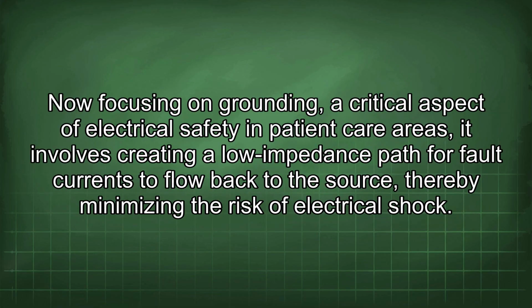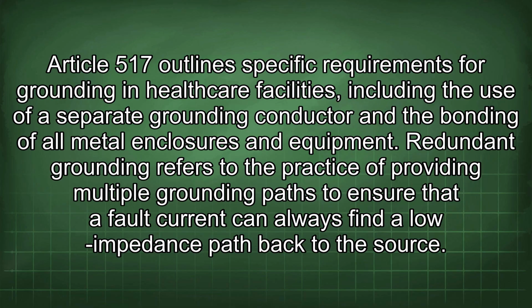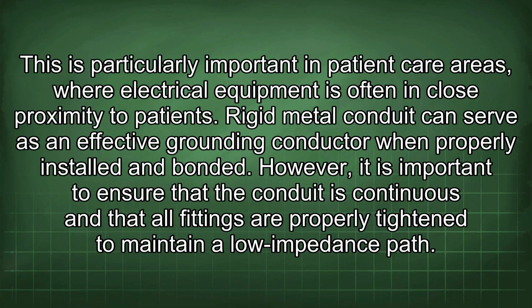Now focusing on grounding, a critical aspect of electrical safety in patient care areas. It involves creating a low-impedance path for fault currents to flow back to the source, thereby minimizing the risk of electrical shock. Article 517 outlines specific requirements for grounding in healthcare facilities, including the use of a separate grounding conductor and the bonding of all metal enclosures and equipment. Redundant grounding refers to the practice of providing multiple grounding paths to ensure that a fault current can always find a low impedance path back to the source. This is particularly important in patient care areas, where electrical equipment is often in close proximity to patients. Rigid metal conduit can serve as an effective grounding conductor when properly installed and bonded.